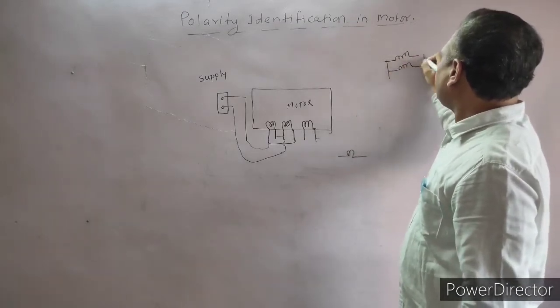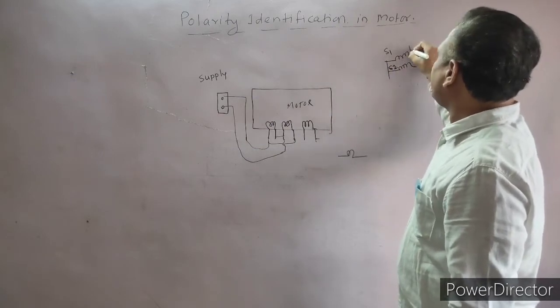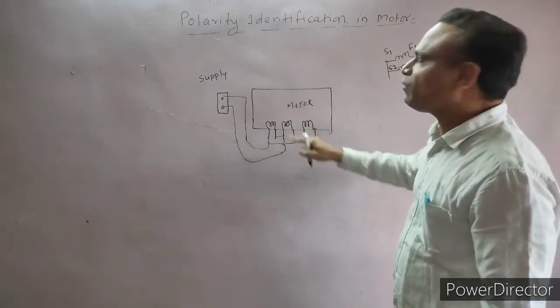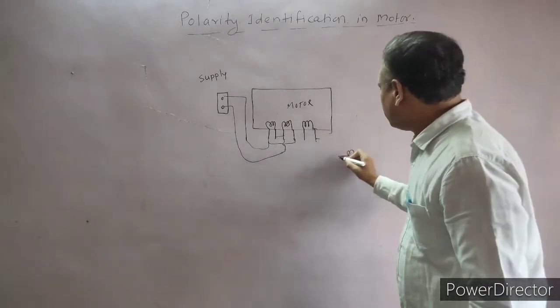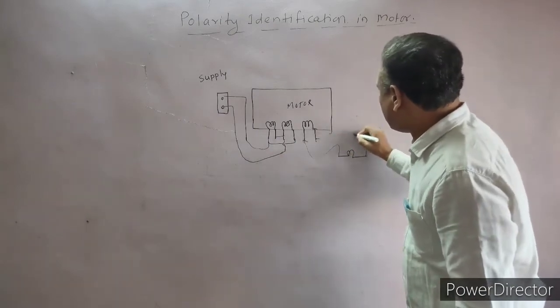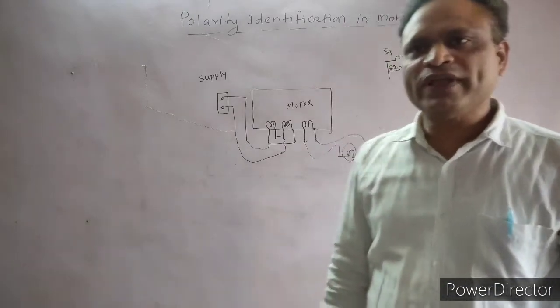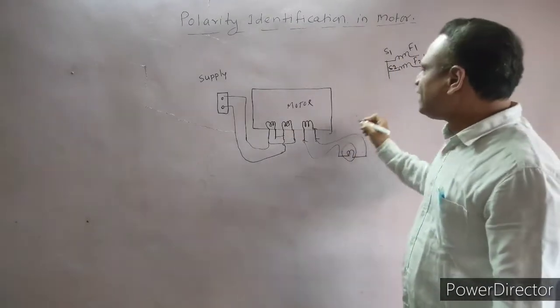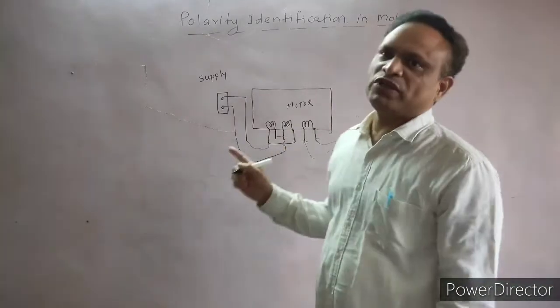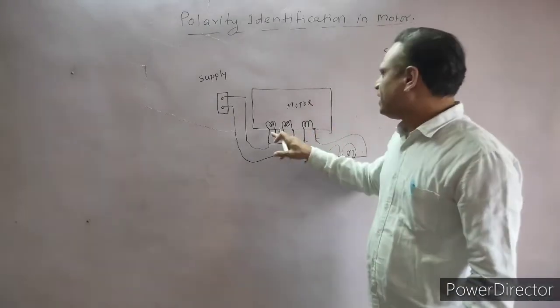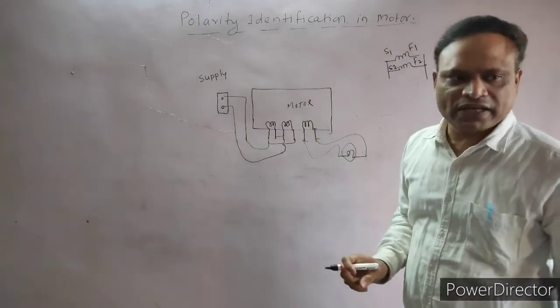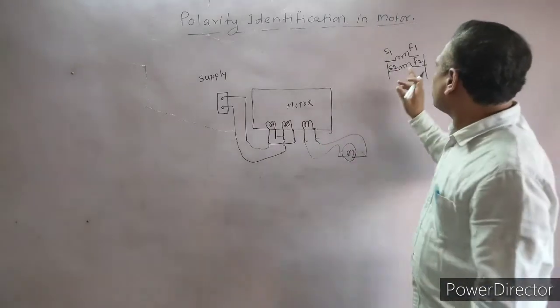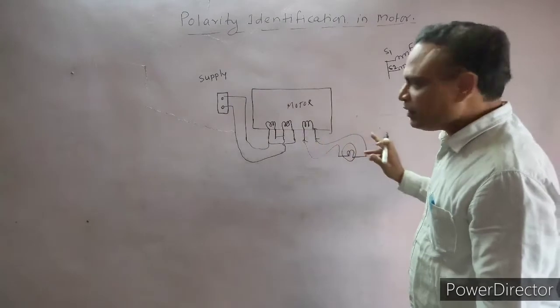There will be a transformer action between the coils. If the coils are connected with starting end to starting end and finishing end to finishing end — that is, in parallel — then when we connect the lamp across the second coil, it will glow. If the lamp glows, we know the starting ends are connected together. If the starting ends are not connected together, there will be series opposition — the EMF induced in each coil will cancel the other — and the lamp will not glow.